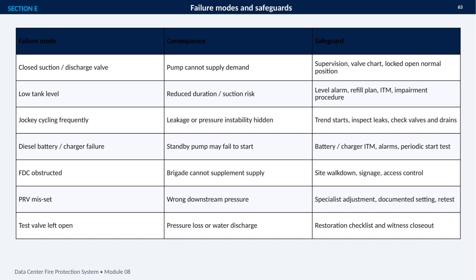Diesel pump reliability depends on battery and charger testing, alarms, and periodic start tests. The fire department connection, or FDC, must remain accessible and unobstructed, with walkdowns, signage, and access control. Finally, pressure-reducing valves require specialist adjustment, documented settings, and retesting. After any test, use a restoration checklist and witnessed closeout to ensure the test valve is actually closed. Restoration discipline is the safeguard that prevents a completed test from leaving the system impaired.